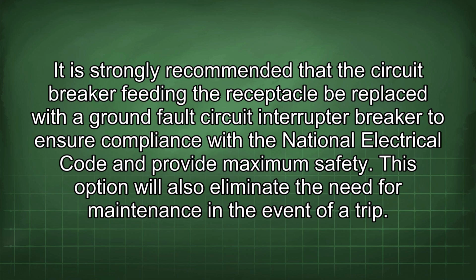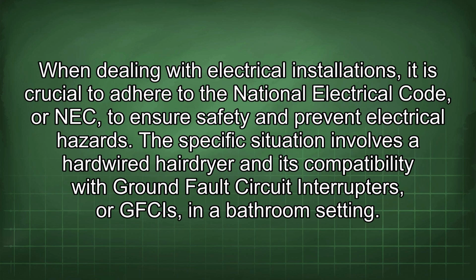It is strongly recommended that the circuit breaker feeding the receptacle be replaced with a ground fault circuit interrupter breaker to ensure compliance with the National Electrical Code and provide maximum safety. This option will also eliminate the need for maintenance in the event of a trip. When dealing with electrical installations, it is crucial to adhere to the National Electrical Code, or NEC, to ensure safety and prevent electrical hazards. This specific situation involves a hardwired hairdryer and its compatibility with ground fault circuit interrupters, or GFCIs, in a bathroom setting.